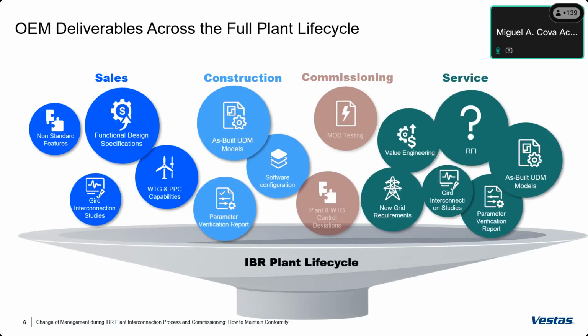When we look at OEM deliverables, this is everything we put into the funnel for the grid operator, the developer, the generator owner, the independent engineering firm, etc. During the sales phase, we negotiate non-standard features and functional design specifications. We support grid interconnection studies and explain the turbine and PPC capabilities. This is important because it's what gets contracted. In the American market, it's fundamental to understand that supply-only contracts, as an OEM, mean our responsibility isn't grid code compliance, but the performance of the generation units. Evaluating grid code compliance relies on the generator owner. So any deviation from what's actually contracted will heavily impact the construction and commercial operation date.